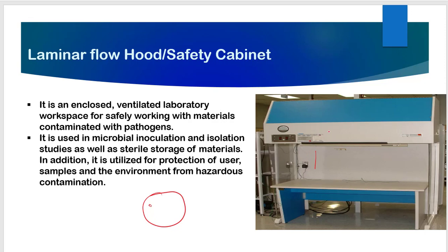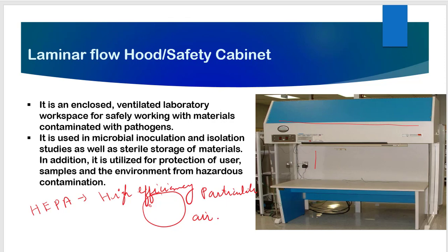In the figure shown, we have a vertical laminar flow because the HEPA filters — H-E-P-A, which stands for High Efficiency Particulate Air filter — are placed in a vertical position. These filters are placed either vertically or horizontally in a laminar hood. The HEPA filters streamline the airflow and filter out harmful bacteria as well as fungal spores from the air, providing a sterilized and clean environment inside the laminar hood.